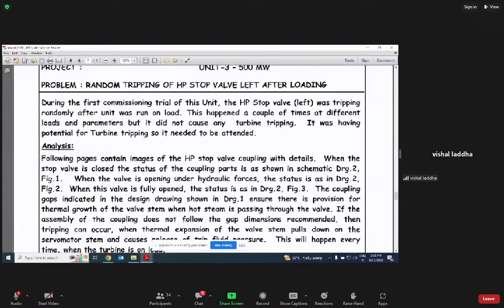After tripping of the stop valve, the turbine was not tripping, because to trip the turbine both stop valves have to close or trip pressure has to go to zero. This happened a couple of times with different loads and parameters, but it did not cause any turbine tripping. It had the potential for turbine tripping, so it needed to be attended. So what was the analysis? What was the line of action we took?